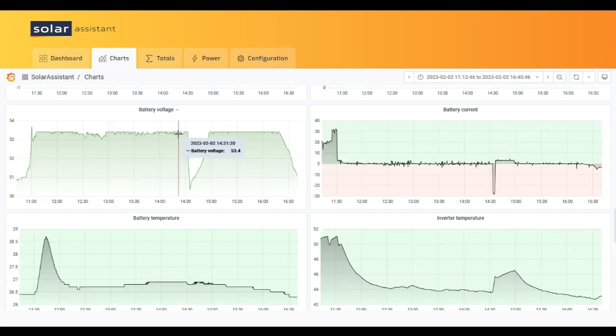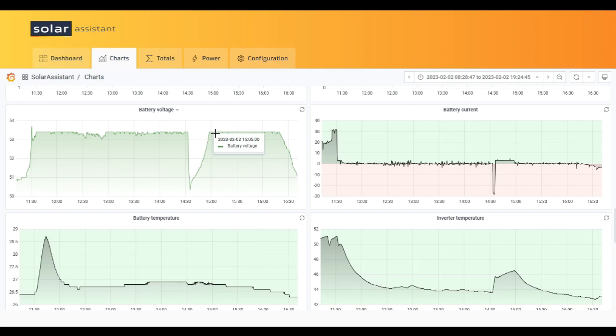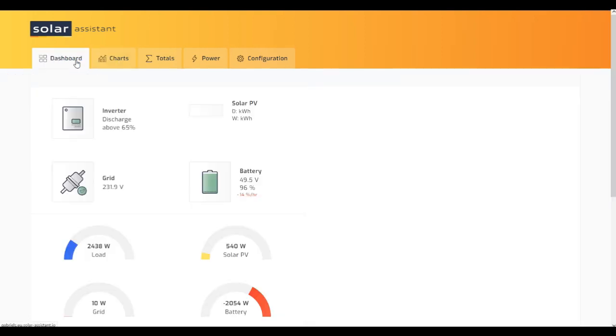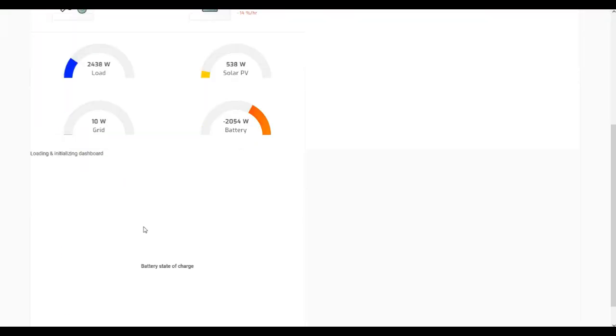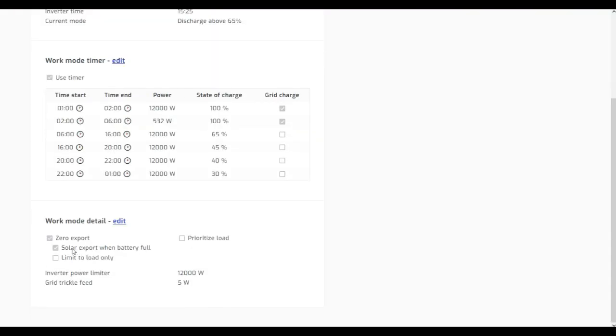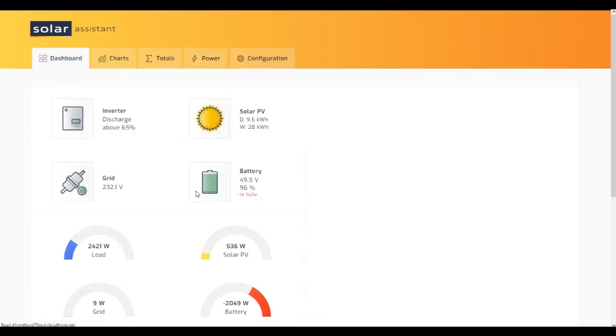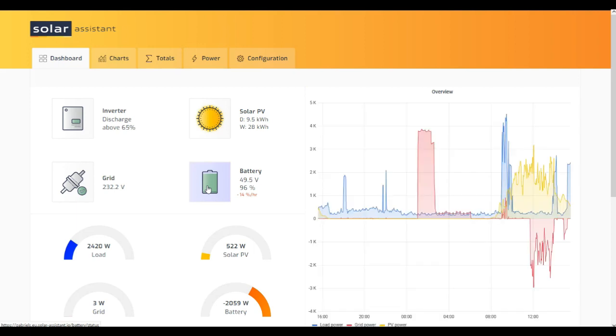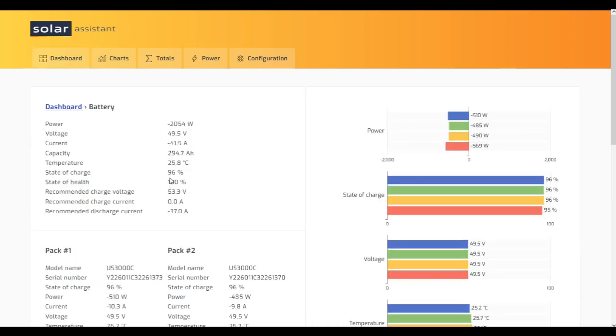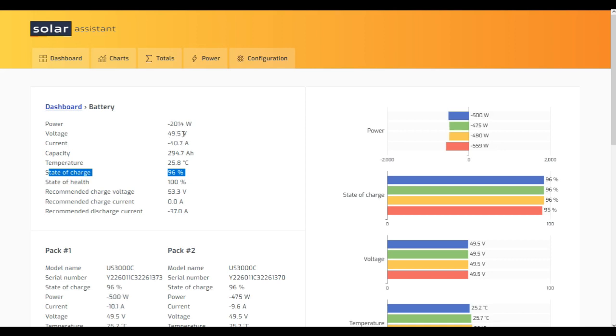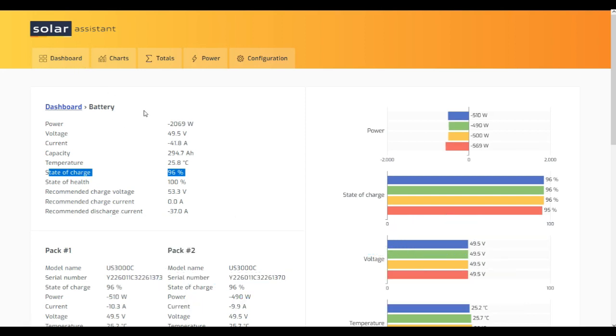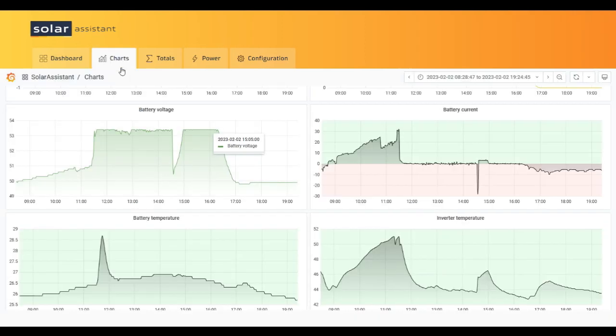As I was saying, the bug is if your solar export is disabled, so you have zero solar export. When the battery is full, what is happening is that the battery will start charging up, it will come to 100% state of charge. The battery goes to 53.3 volts and if everything works correctly, the battery will start dumping power back to the grid to stabilize the voltage somewhere around 51 or 52 volts, the floating voltage of the BMS. Well, if the export to grid is disabled and the battery cannot dump the extra power, this overvoltage will happen as you can see here.